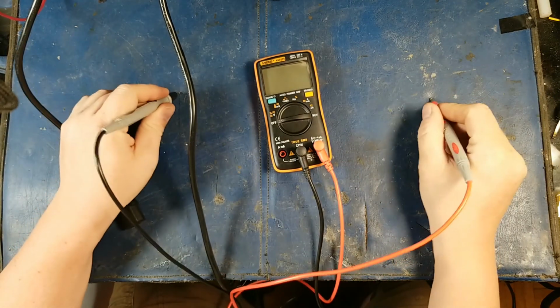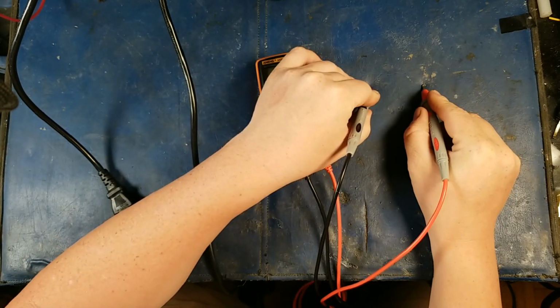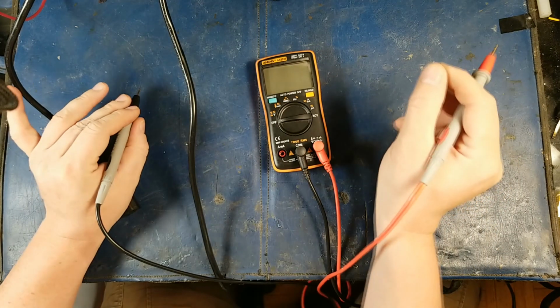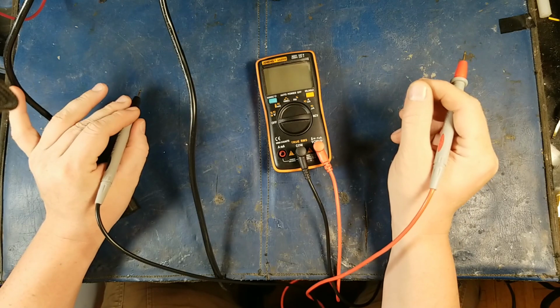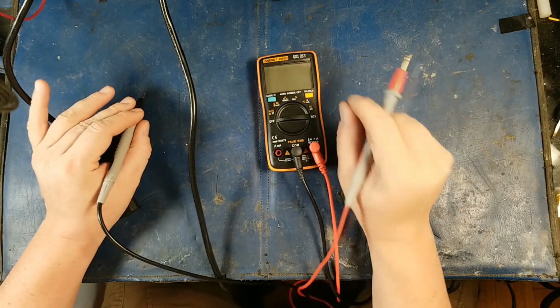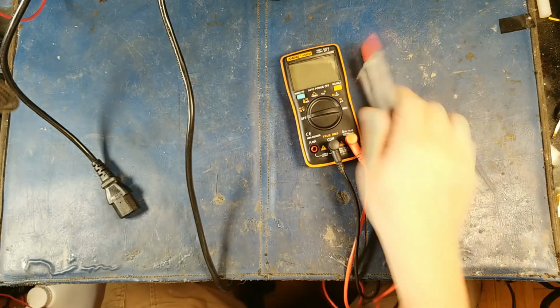If that's the case, you simply adjust the governor on it with the probes plugged into your phase. I like going across both of them on the 220 side of things rather than half going to 120. Then you can adjust the duty cycle of your governor while you're looking at this, and get the frequency back to where it belongs.